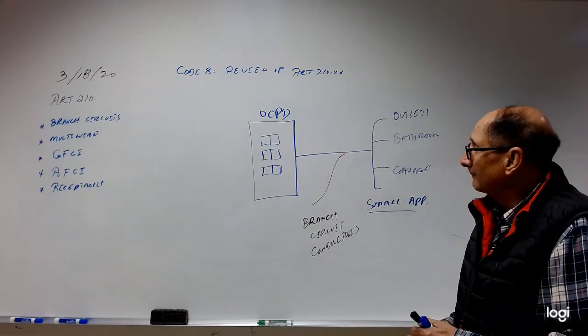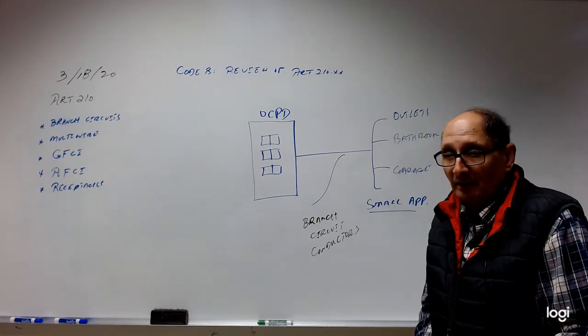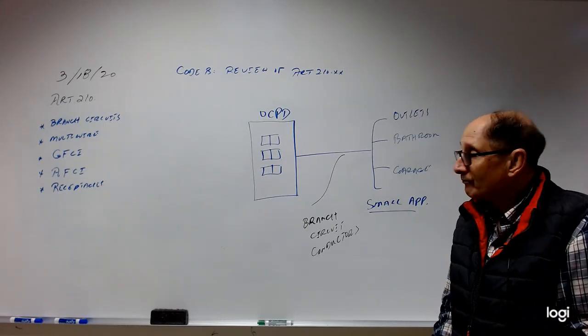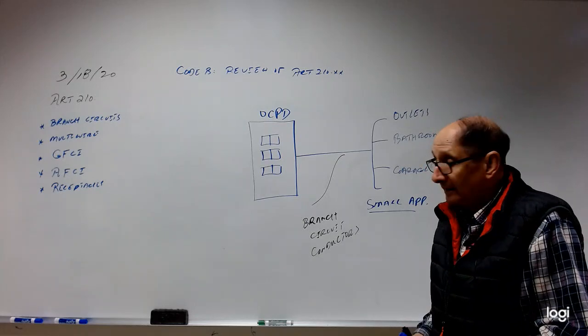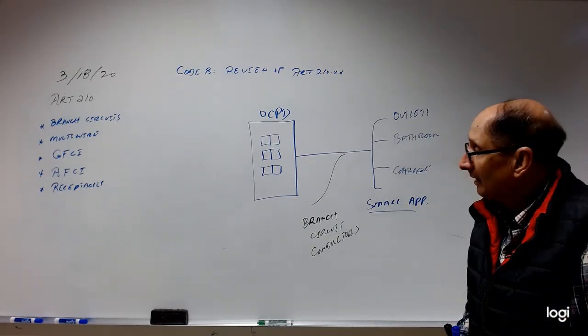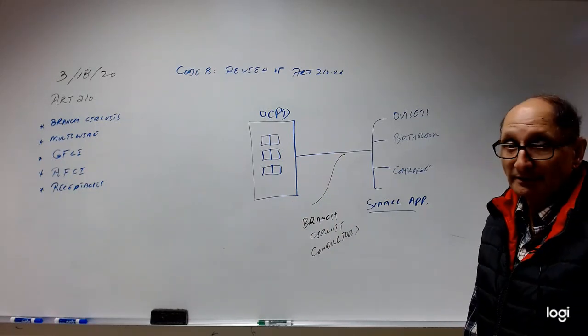That means if something happens to the neutral, both ungrounded conductors, which are hot wires, are going to be disconnected. They must provide line to neutral loads. They must be grouped together. So these are some of the requirements when it comes to multi-wire branch circuits.